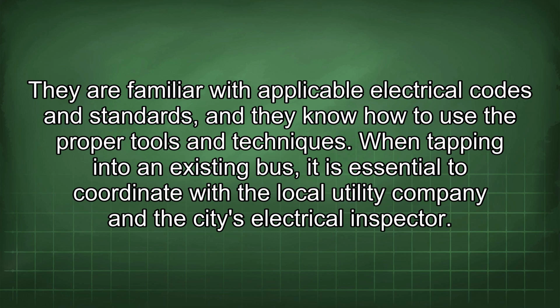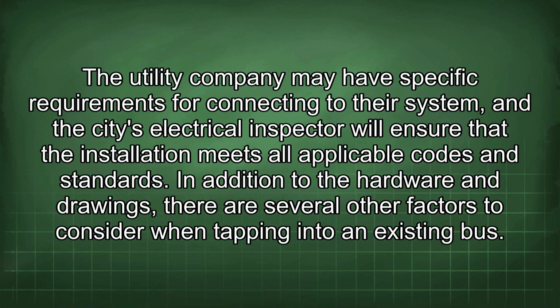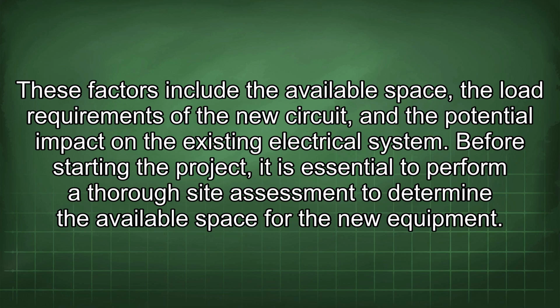When tapping into an existing bus, it is essential to coordinate with the local utility company and the city's electrical inspector. The utility company may have specific requirements for connecting to their system, and the city's electrical inspector will ensure that the installation meets all applicable codes and standards. In addition to the hardware and drawings, there are several other factors to consider when tapping into an existing bus.